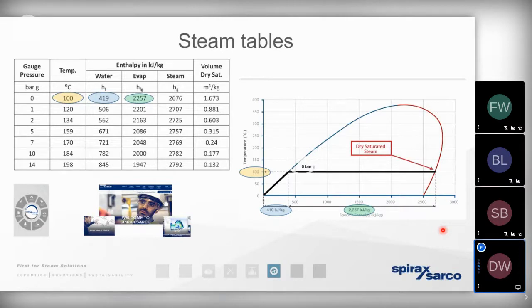So you can appreciate that wet steam is by far and away one of the biggest problems that we can encounter whenever we're talking about using steam for heat exchange purposes. All of the steam tables, all of the calculations we make are based on the assumption that that steam is going to be dry saturated steam. If it's wet steam, then all bets are off.